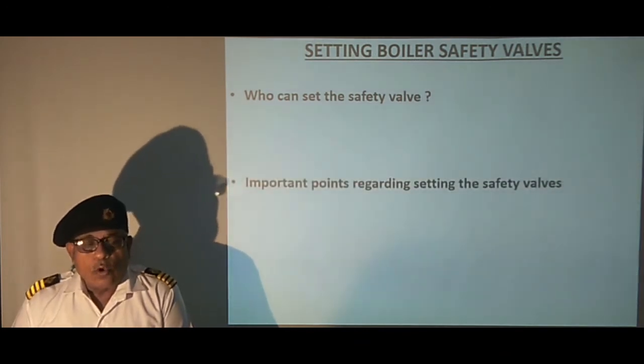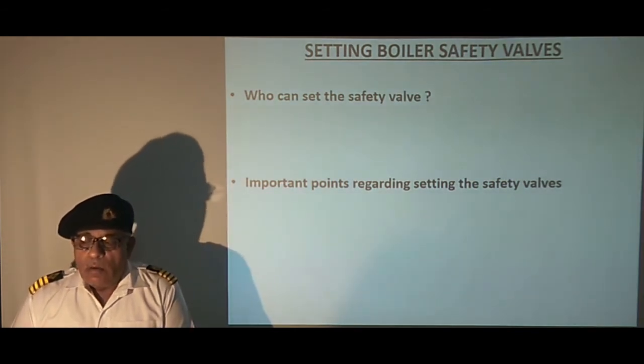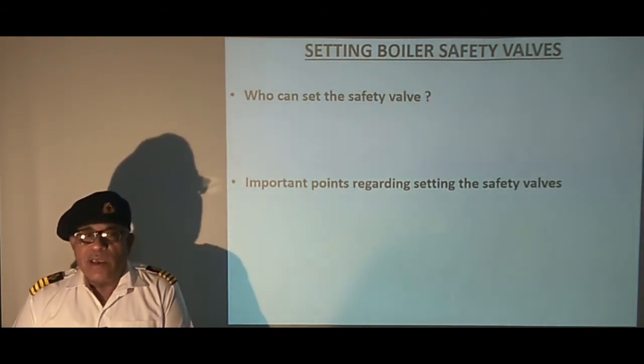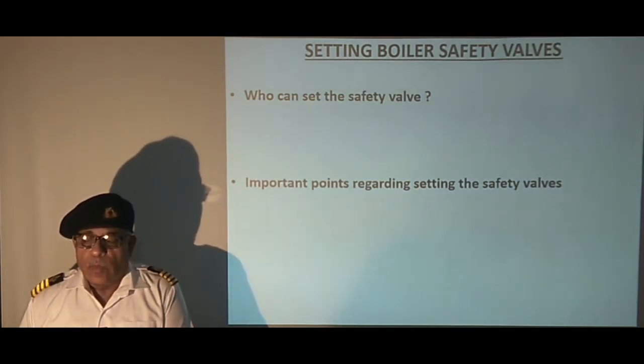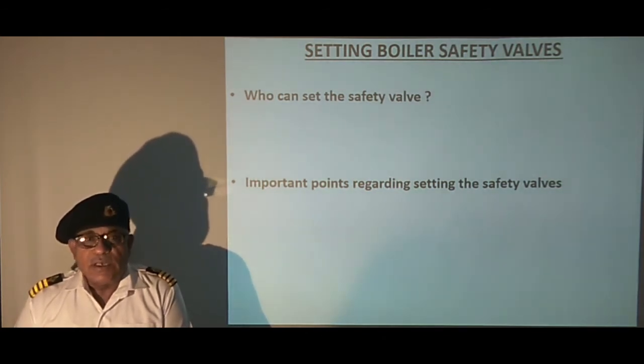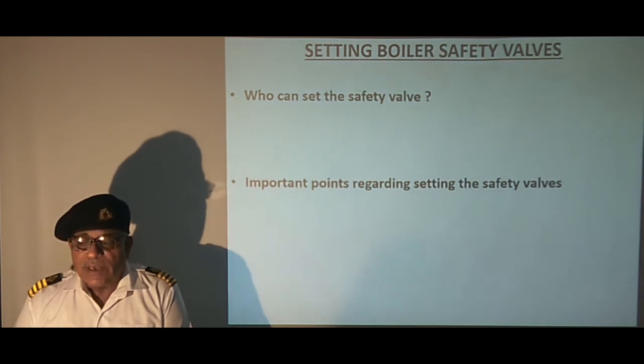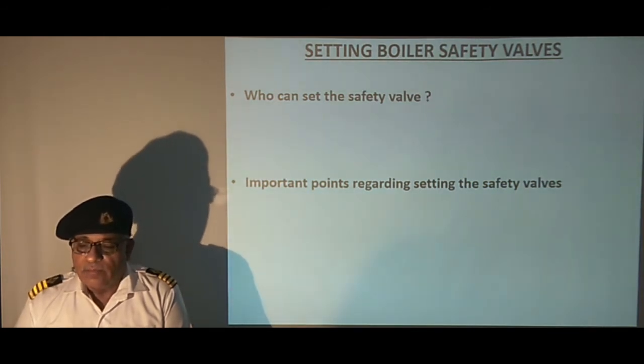Now we will note important points regarding setting of the safety valve. Pressure should be set by a certified calibrated pressure gauge. Free operation of the easing gear must be confirmed before setting the safety valve. Each safety valve is set independently.